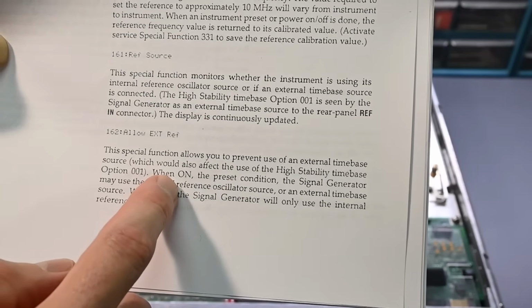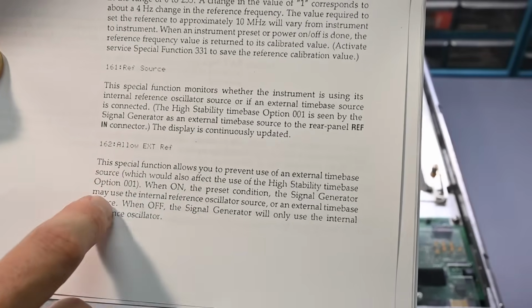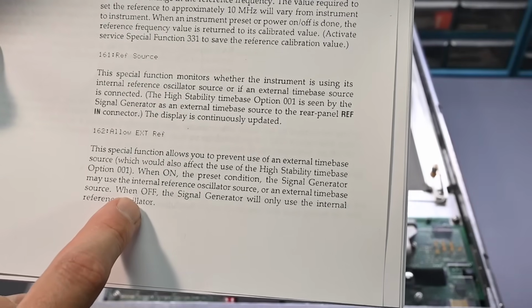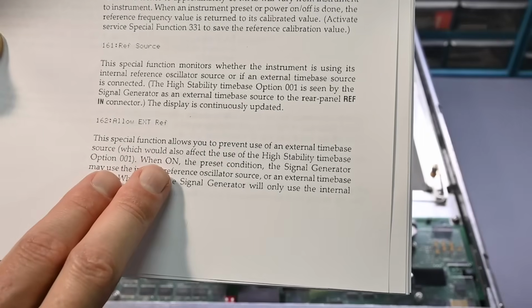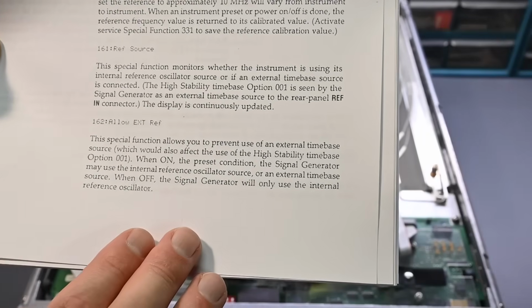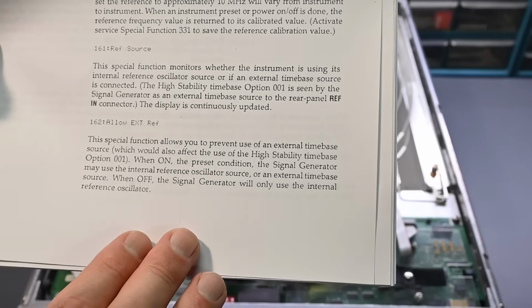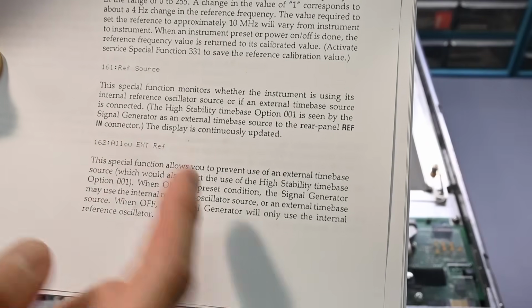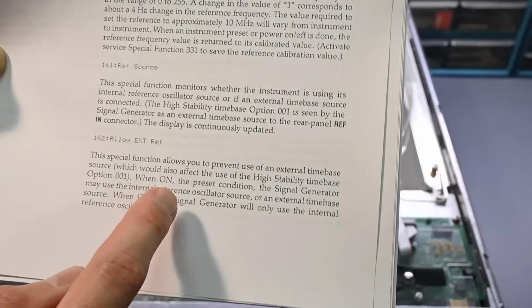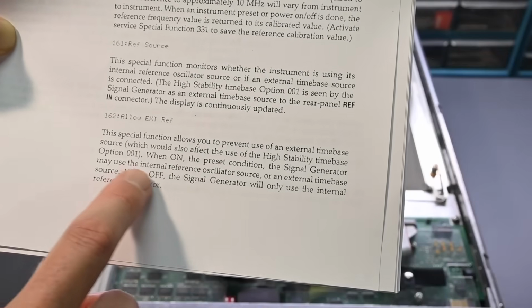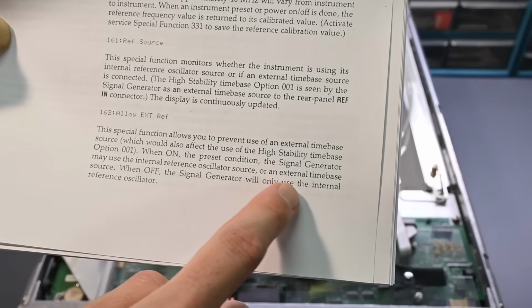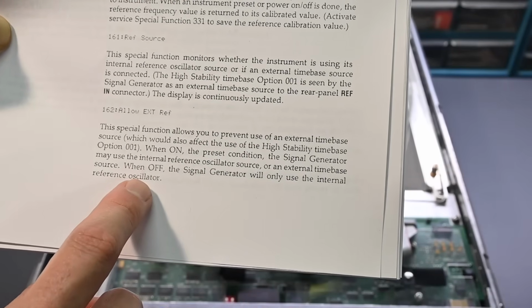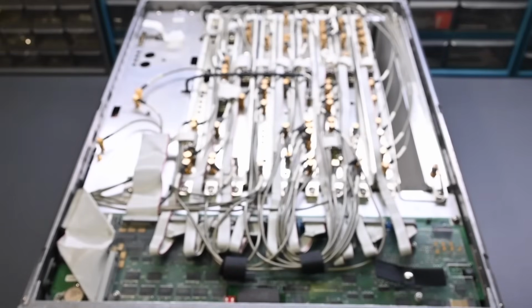So unless this has been turned off, and I'll definitely have to check these and make sure that this is set correctly. But because the memory was lost and the battery seemed to have wiped everything out, and I got that memory cleared error, I would think that these would reset back to the factory default anyways, but definitely want to double check this. And it says when it's turned off, the signal generator will only use the internal reference oscillator. So let me move you down to the rear panel connectors and we'll take a little bit closer look.